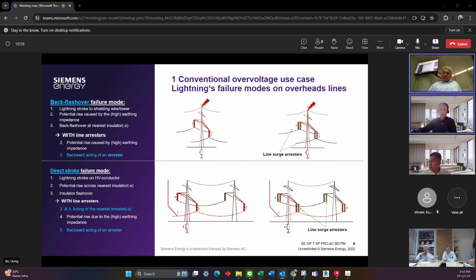Now we are talking about microseconds, a very, very short duration. And in such a short duration, the insulator will receive a very high overvoltage, because we have a high footing resistance. Then the inductive voltage drop across the cross arm to the transmission line will be over the basic insulation level, and it will lead to flashover on the insulators. Since the energy tries to go to ground but cannot discharge quickly enough, we call it back flashover, because the energy will go back to the cross arm and it will establish overvoltage across the transmission line.